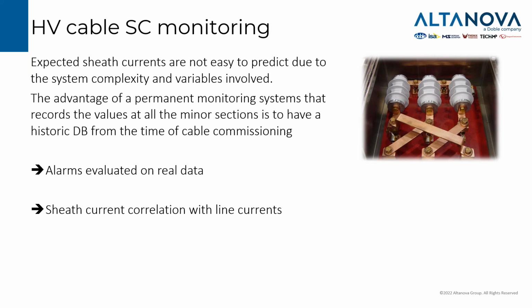Unfortunately, this method is not so effective when we perform spot testing, because the sheath current simulations are not so easy compared to the real condition. Since there are so many parameters involved because of the installation, we can have some doubts when taking just a single acquisition.